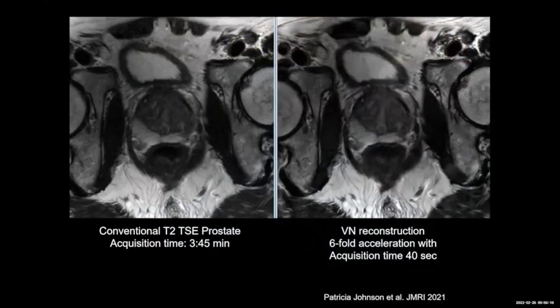To show you an example, initially we trained our network on 3 Tesla data because we just had a lot more data to train our network. This is a conventional T2 TSE of the prostate. Its acquisition time is about 3 minutes and 45 seconds. This is a 6-fold accelerated reconstruction, and basically the acquisition time is about 40 seconds, which has similar image quality to the conventional acquisition.